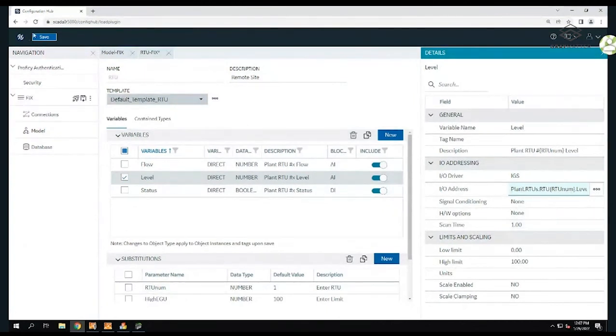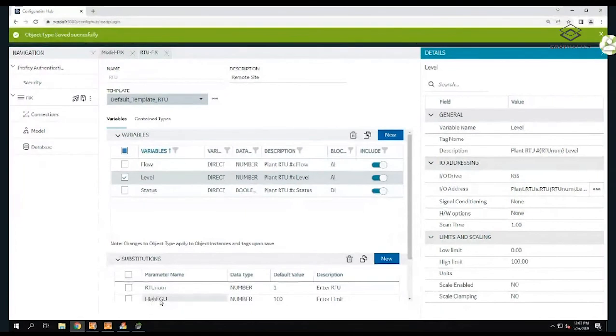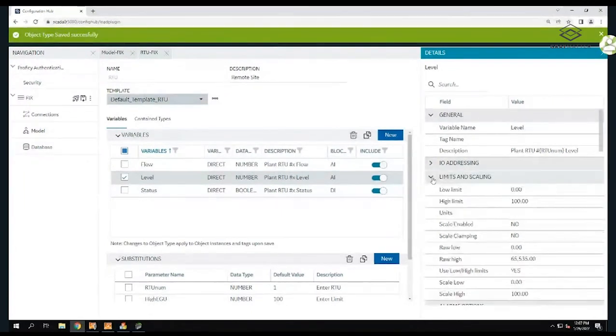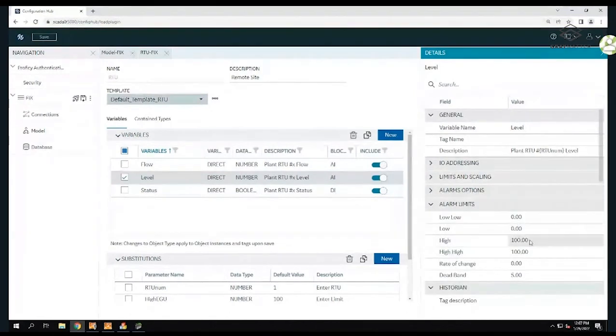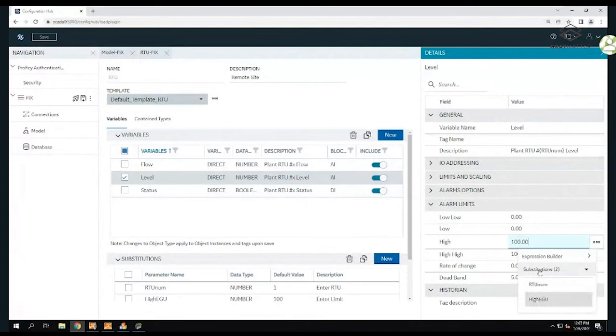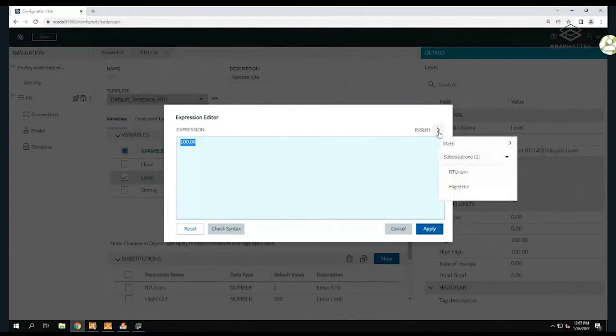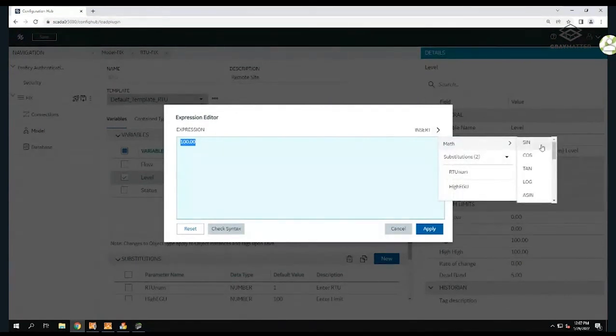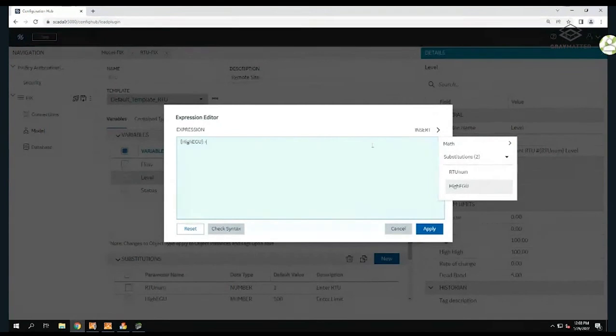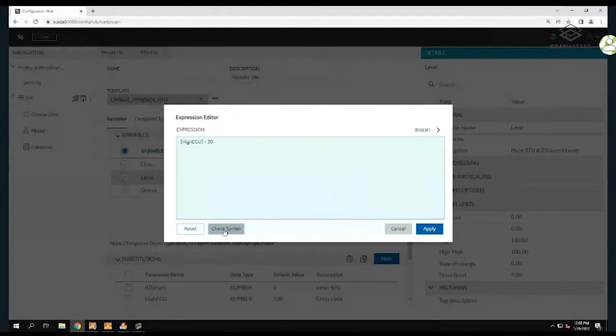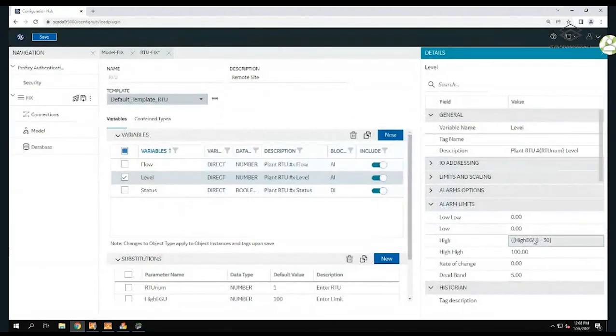I have the high engineering units, and I'm going to go down to my alarm limit. You can actually build an expression here, so instead of putting a full substitution, I'll go into Expressions. This brings up an expression builder where I can build a logical expression using math or Boolean functions. In this case, I want to take my high engineering units and subtract 30 - that will be my alarm limit. I check syntax, hit apply, and it puts that placeholder in my alarm limit.